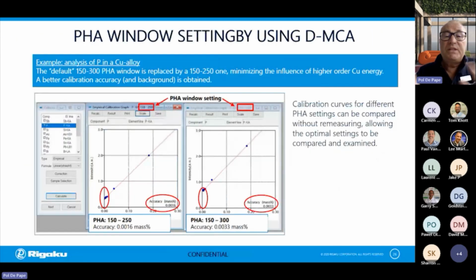Depending on how we set the window, on the right-hand side, we can see a calibration curve using a 150 to 300 window. We can see quite a high background here and an accuracy of 33 ppm for the phosphorus, which is low in concentration. If we use a PHA window 150 to 250, we can see, first of all, a much lower background, so we are really reducing the influence of copper, and an accuracy 2 times better, so 16 ppm. So calibration curves can easily be changed simply by changing this PHA window and without having to do an additional measurement.